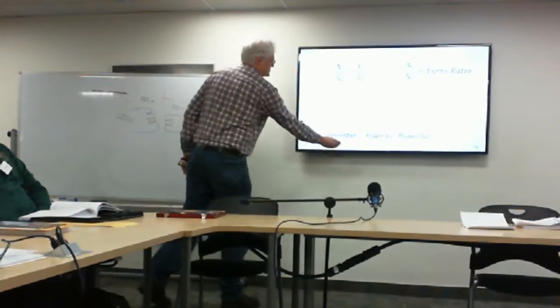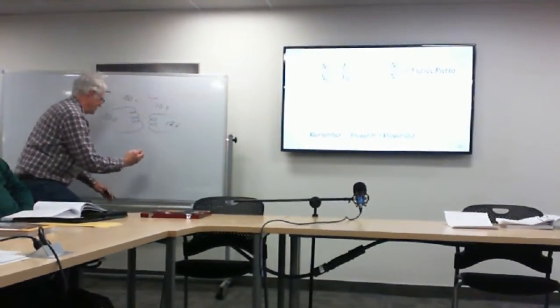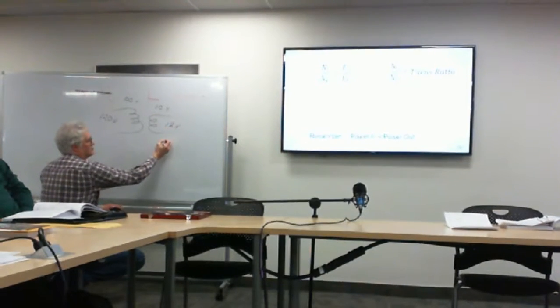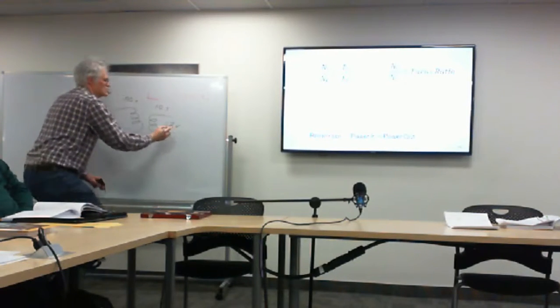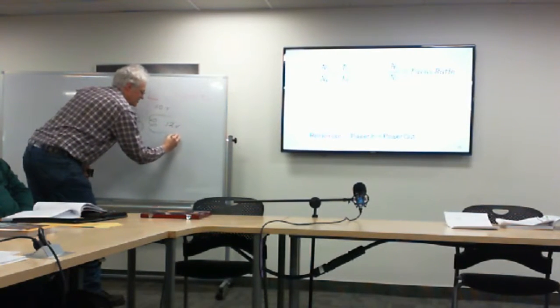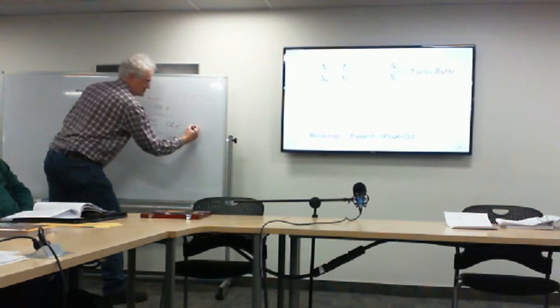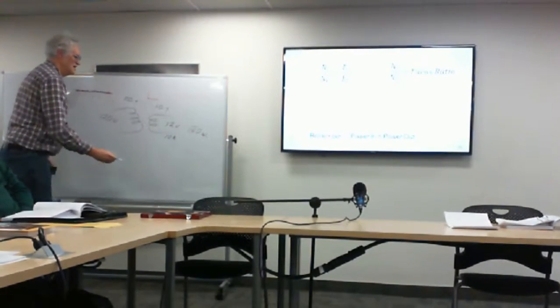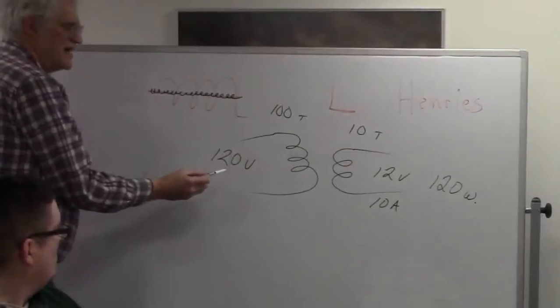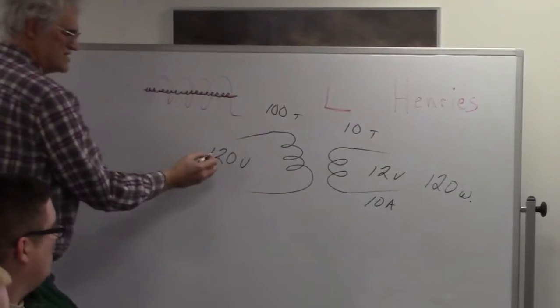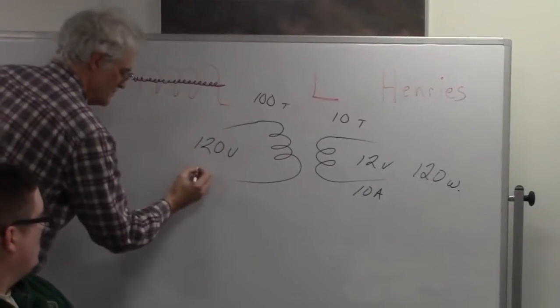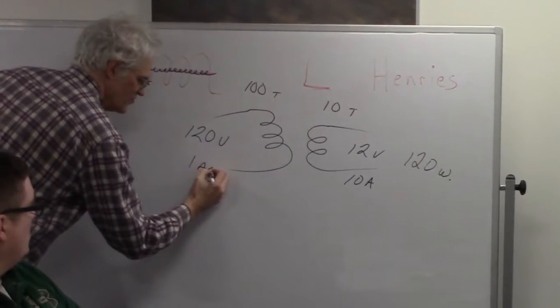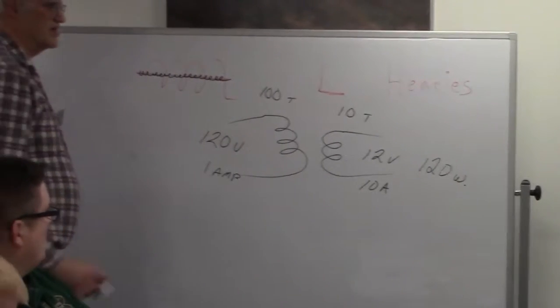Remember: power in equals power out. Say we have 12 volts out drawing 10 amps — that's 120 watts. The power in has to match, so 120 watts divided by 120 volts gives us one ampere of primary current. Everything is in ratios.